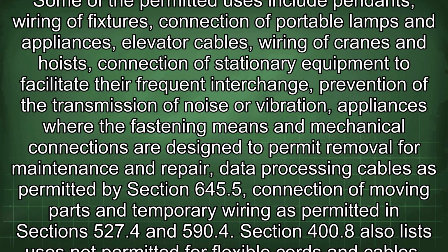Some of the permitted uses include pendants, wiring of fixtures, connection of portable lamps and appliances, elevator cables, wiring of cranes and hoists, connection of stationary equipment to facilitate their frequent interchange, prevention of the transmission of noise or vibration, appliances where the fastening means and mechanical connections are designed to permit removal for maintenance and repair, data processing cables as permitted by Section 645.5, connection of moving parts, and temporary wiring as permitted in Sections 527.4 and 590.4.